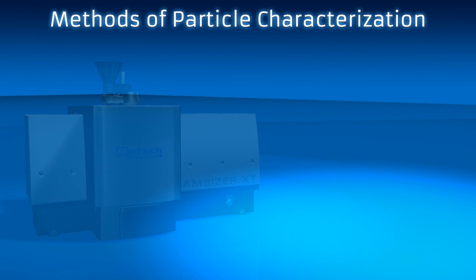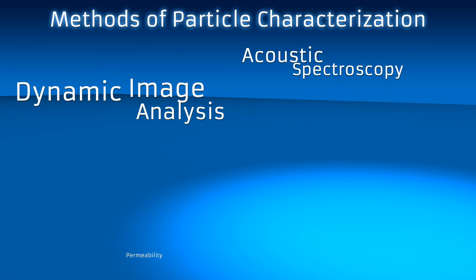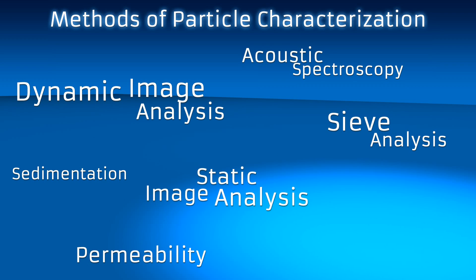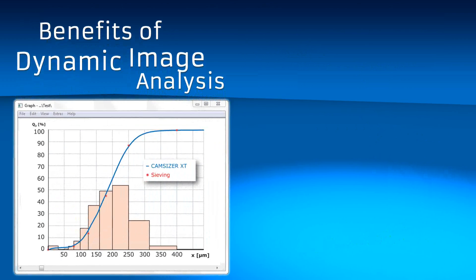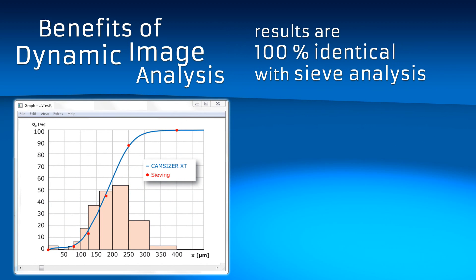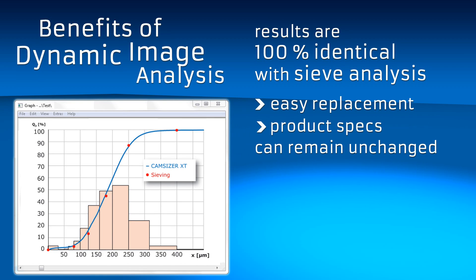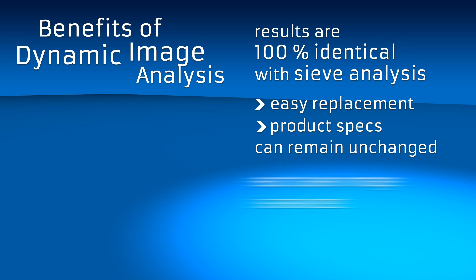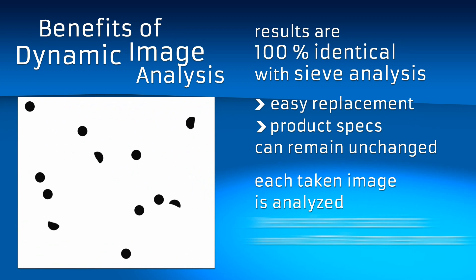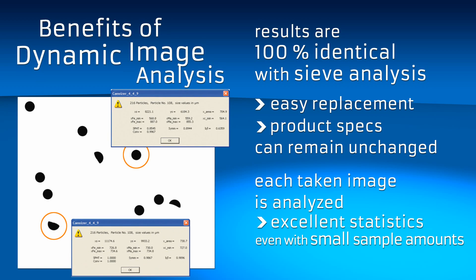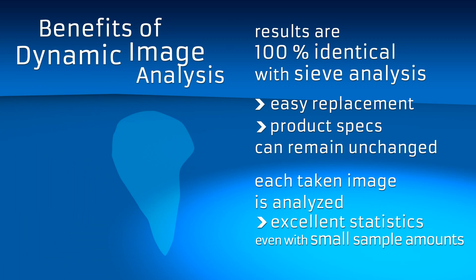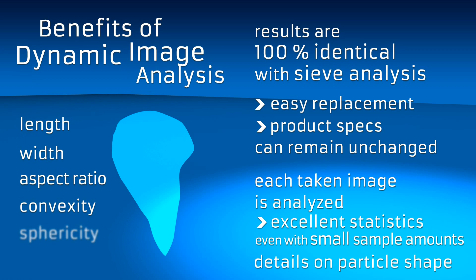Besides dynamic image analysis, the market offers instruments using other analysis methods which provide information on particle characteristics. But what are the benefits of DIA? Results obtained with the CamSizer XT are 100% identical with sieve analysis. Thus, the replacement of the time-consuming and unreliable sieving process with the CamSizer XT is straightforward, and the product specifications can remain unchanged. Due to the fact that each particle in each image is analyzed, excellent statistics are obtained in a very short measurement time. The high detection efficiency ensures reliable results even with small sample amounts. Furthermore, the CamSizer XT provides details on the shape of the particles — information that other analysis methods cannot deliver.